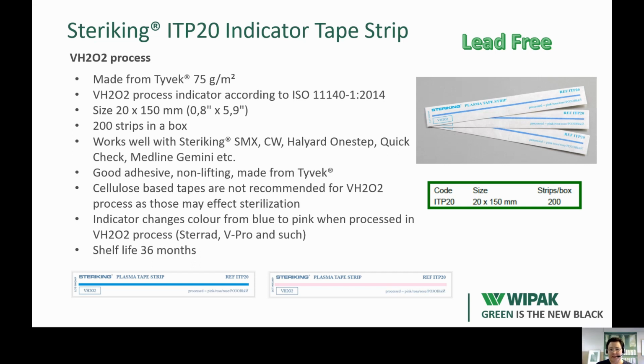And as this is intended for hydrogen peroxide sterilization, it's also working very well with all the synthetic wrapping materials like our SMX and Halyard and Medline, etc. And then, like said already, it has the same color that we have in our Tyvek pouches and rolls, and therefore the color changes from blue to pink when exposed to Sterrad and V-Pro sterilization cycles. Shelf life of these tape strips is 36 months.